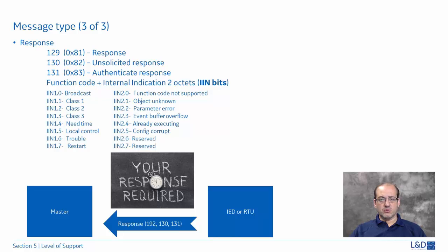Those IIN messages are basically utilized by the master in order to manage what polling needs to happen to the device, or to inform the person who's taking care of the system to dispatch the right engineer to take the right action at site with that device.